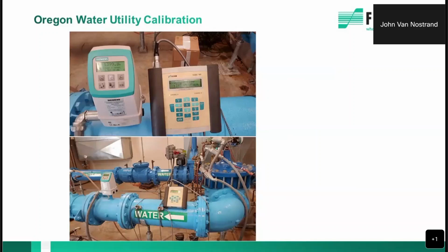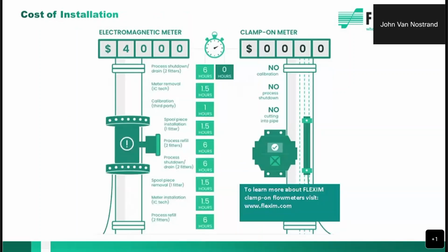Here is a picture of just a typical verification of calibration check. Look at the straight run here. There's very, very little. Again, we have the capability to dial in exactly the distance between the flange to the center point of the transducers, and we can offset any disturbances upstream from the transducers. Magmeters here, you're looking at the difference, you can see they're right on the money. 1392, 1399, they're well within 1%. So that Magmeter passed calibration.